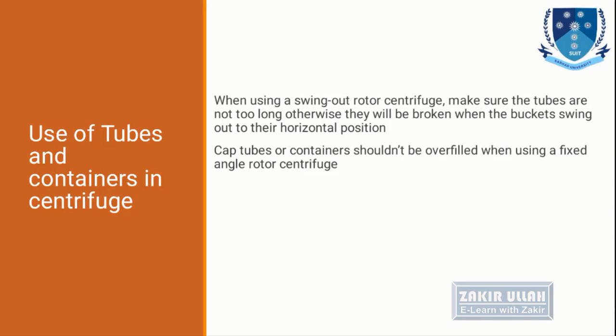And always keep tubes or containers from being overfilled when using a fixed angle rotor head centrifuge, because when we overfill such tubes, the solution can spill over, or the tubes may break due to the force exerted during centrifugation. So we have to try not to overfill or put an excess amount of solution in a tube.